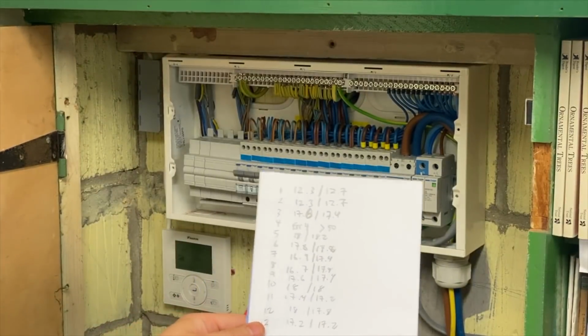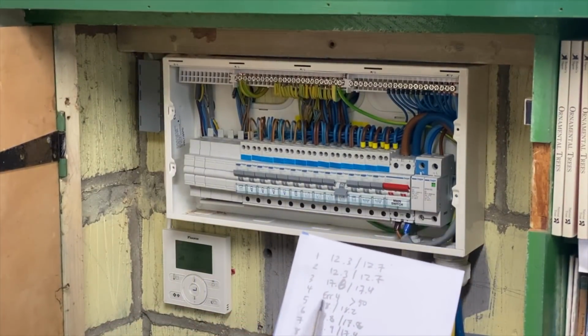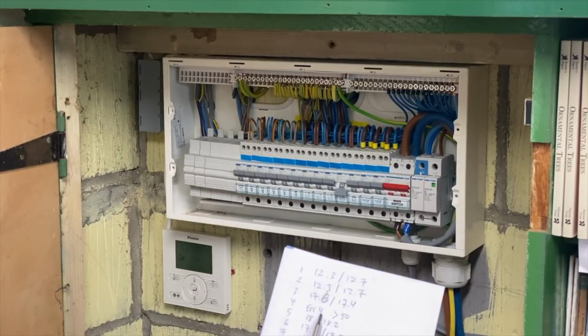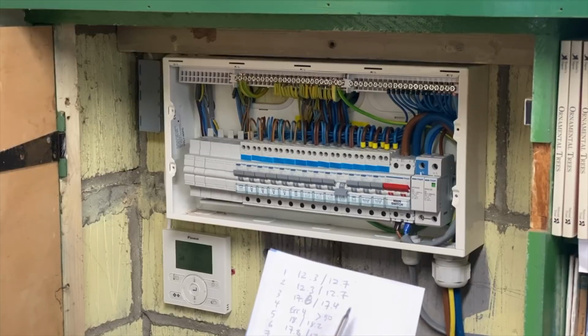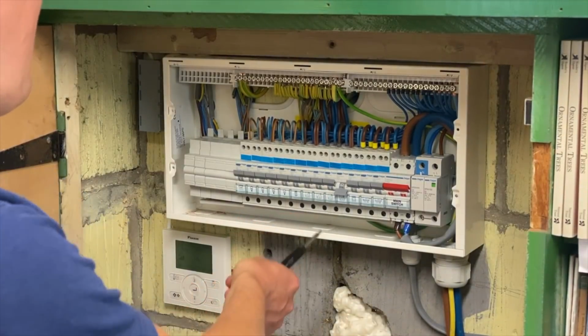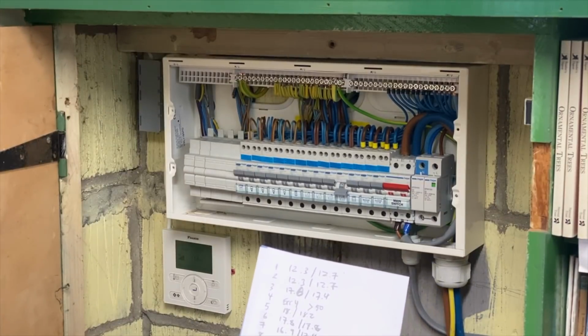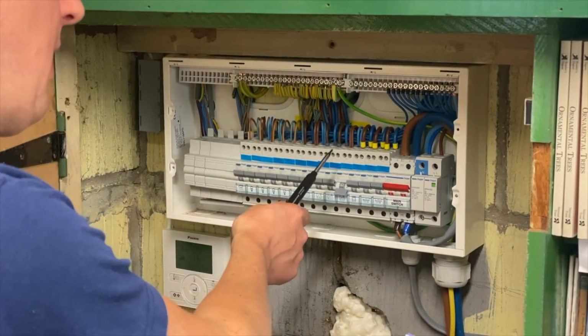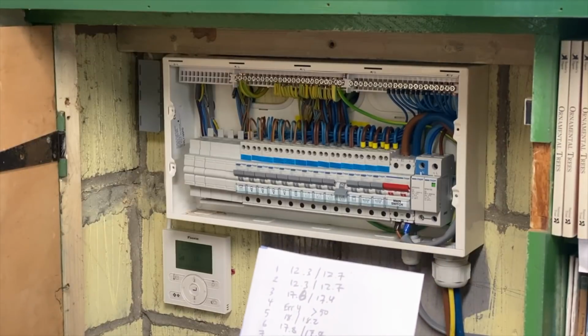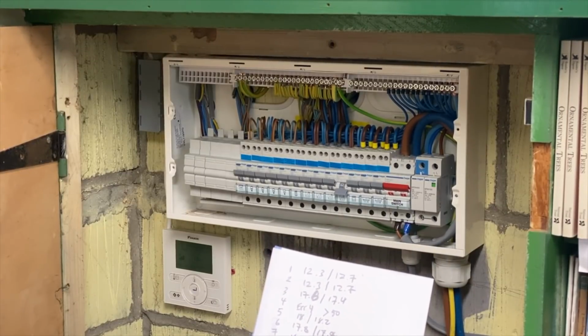Right, so I've got all my readings here, and you'll notice that actually circuit 4, the testing there gave me error 4 on my tester, and then the 5 times testing was more than 50 milliseconds. So I've left that circuit off, and I'm going to swap out the RCBO. Hopefully it's just a faulty RCBO, and then hopefully that should do the trick.